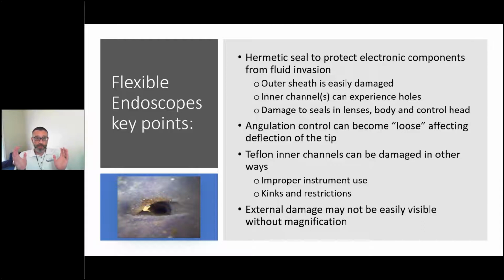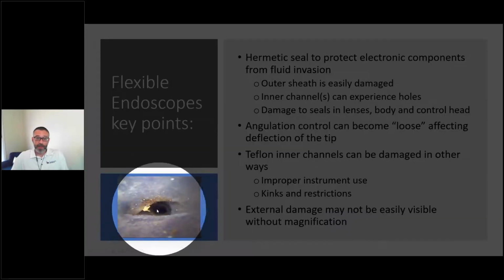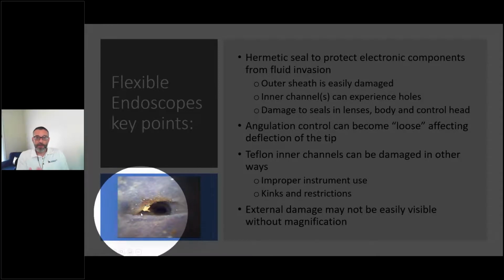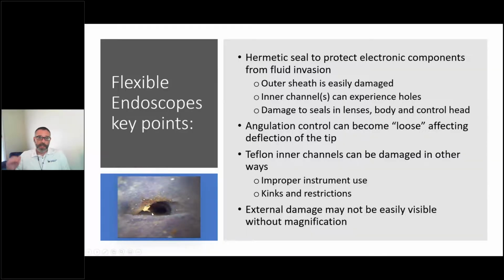So when someone says don't coil your large endoscope smaller than a basketball or soccer ball, it's because it creates what you see on the left. Jahan showed a picture, but here's another one. At that pinch point, debris collects, because that's just a speed bump to a cleaning brush.